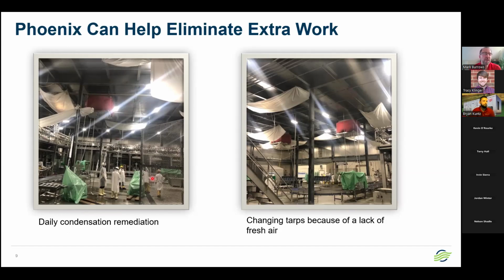So also, when you guys are going to your plant sites, it's critical on this to notice how much exposed metal we have, right? Corrugated metal, all the structural beams and whatnot. What a great place to catch or to have the formation of condensation, right? So there's 3 types of ceilings that we walk into. In a perfect world, it would be the false or the 4-inch IMP panel ceiling, which is great. Those are what we'd like to see. In this case, this was never intended to be a production room.